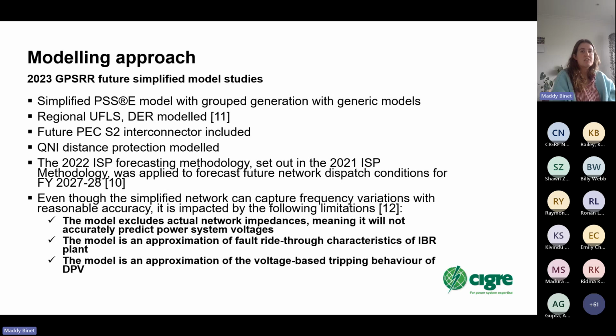So as I touched on before, even though the simplified model can capture frequency deviations fairly accurately, it does have a number of limitations. Firstly, it excludes the actual network impedances, as lots of the network is lumped, so it can't accurately predict power system voltages. That means the model is only an approximation of the fault ride-through behaviour of IBR plants, and also of voltage tripping behaviour of DPV and loads.